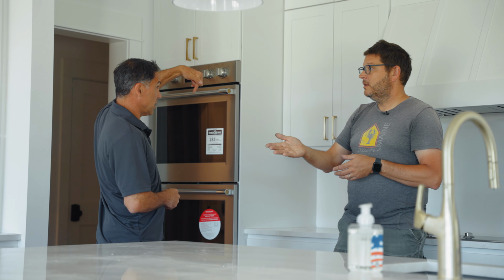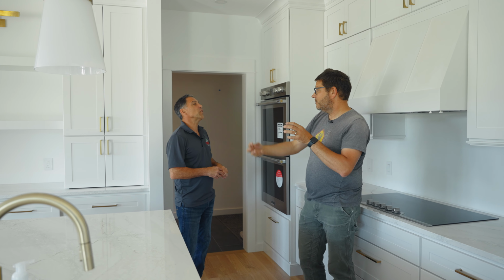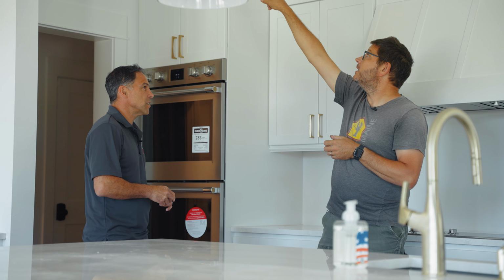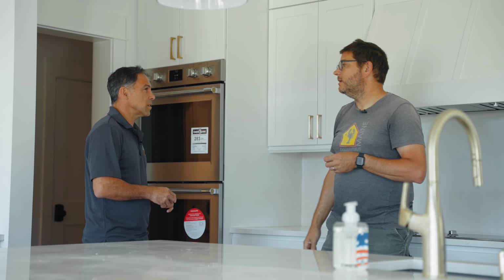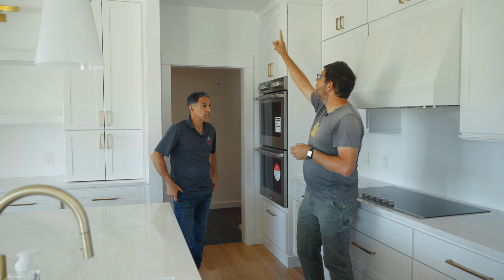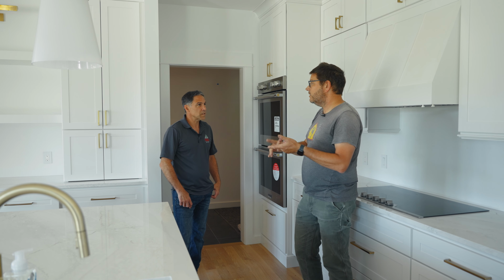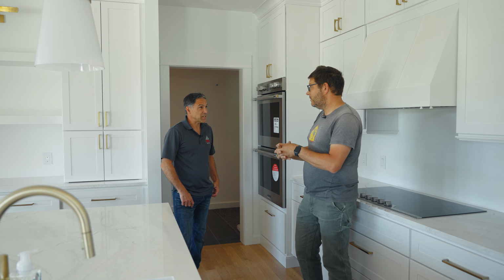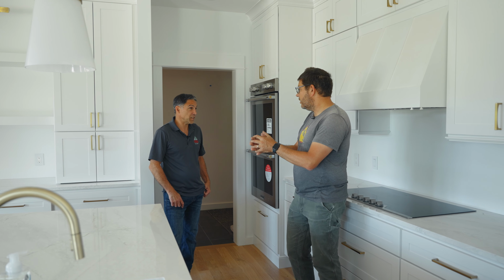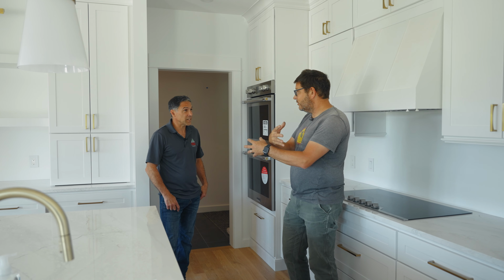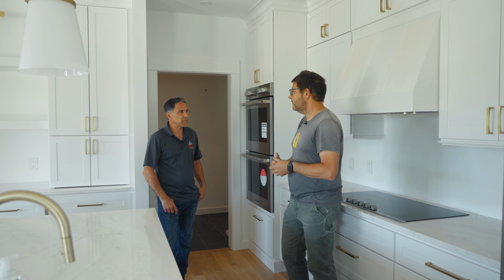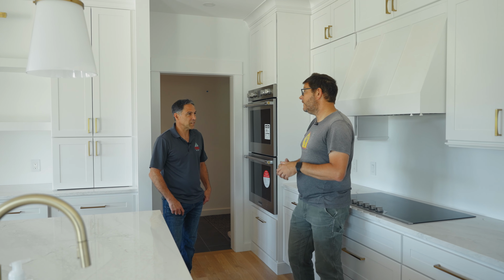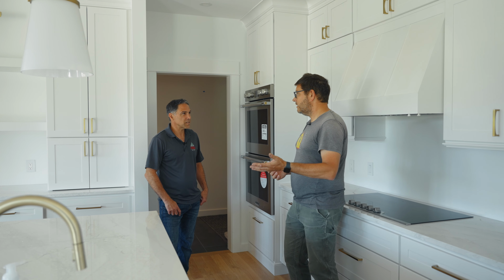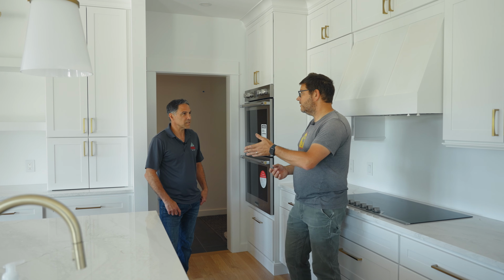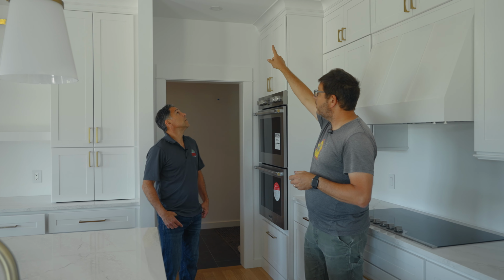The fresh air is coming in through that filter protecting it, while the air going out gets pulled out of here at about 32 CFM, 32 cubic feet a minute, continuously. But there's a little filter in there too, because when you're pulling air out of the kitchen, it's got grease and particulates in it - you don't want that getting into the exchange core. You want to keep that clean. You wouldn't think to filter the air going out, but you've got to keep the equipment clean. That's one reason I like this system versus a lot of cheaper systems out there that don't protect the core - if you don't do the filtration, every 6 months you'd need to pull it out and clean the whole thing. So that's exhaust air, since we're in the kitchen.